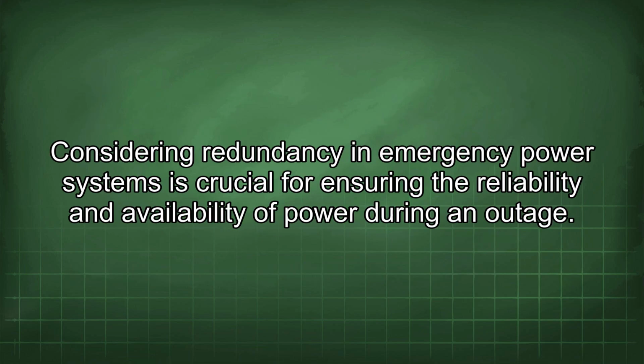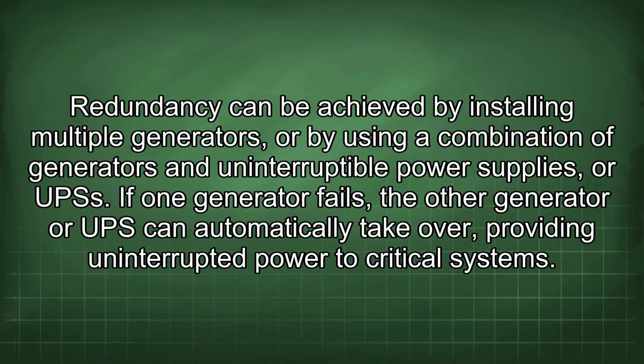Considering redundancy in emergency power systems is crucial for ensuring the reliability and availability of power during an outage. Redundancy can be achieved by installing multiple generators or by using a combination of generators and uninterruptible power supplies, or UPSs. If one generator fails, the other generator or UPS can automatically take over, providing uninterrupted power to critical systems.